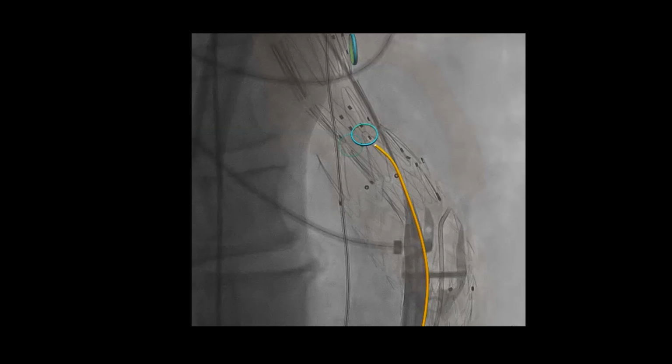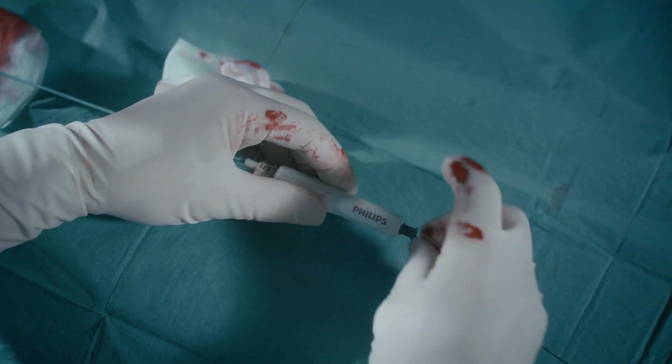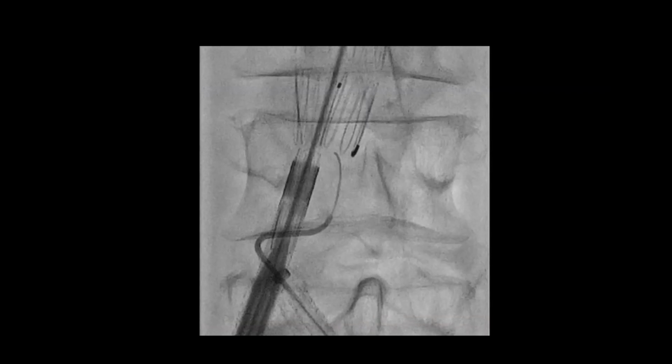And to be able to do so, currently those optical connectors that you need are way too big. So our focus has been on creating an optical connection that has the same size as the diameter of a guide wire. It is really small compared to what is commercially available. So normally a guide wire looks like this. The ones in backloadable are up to 3.2 meters.